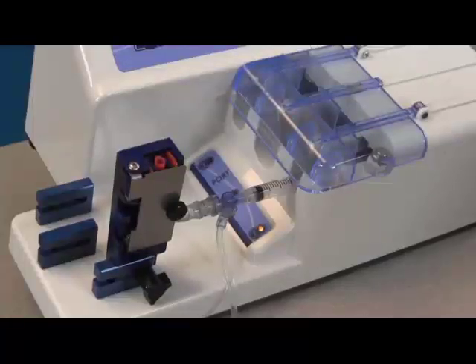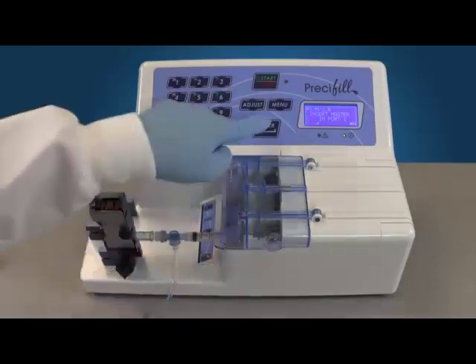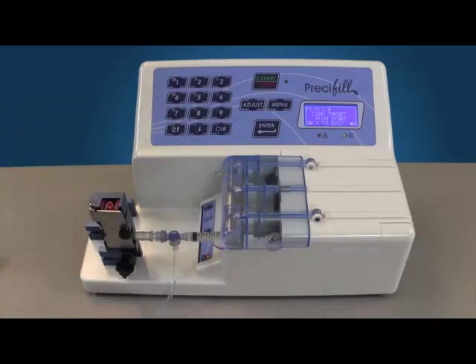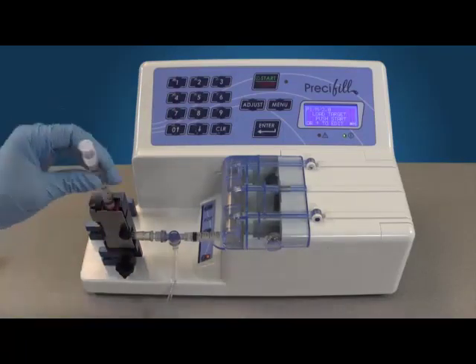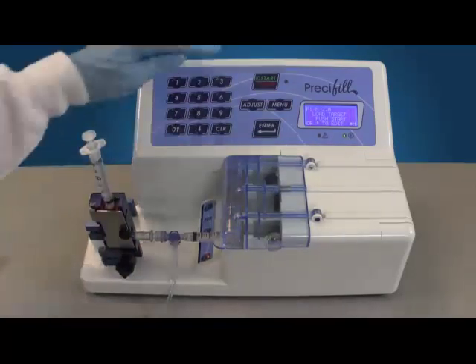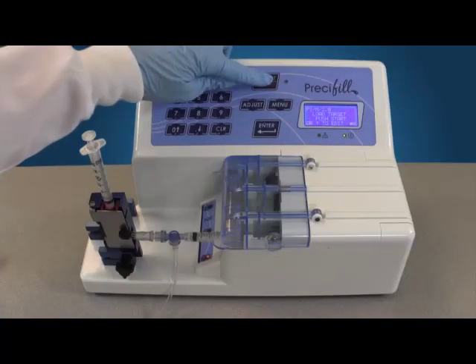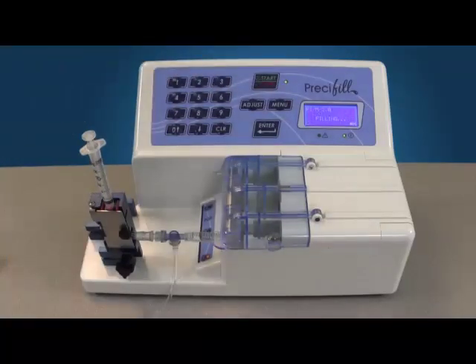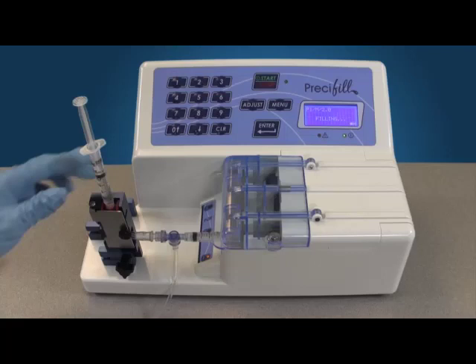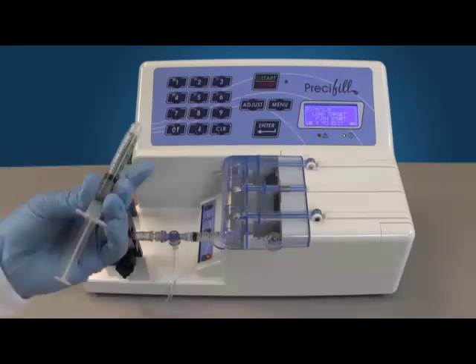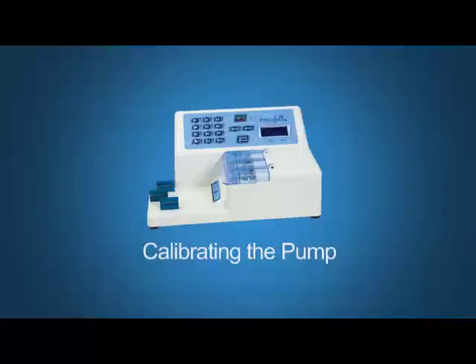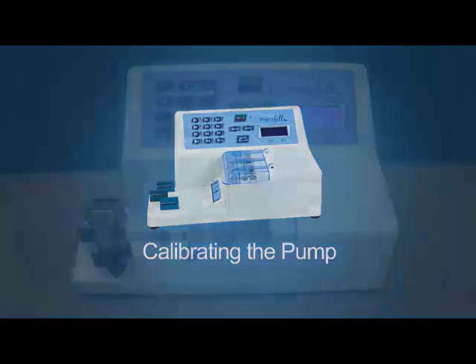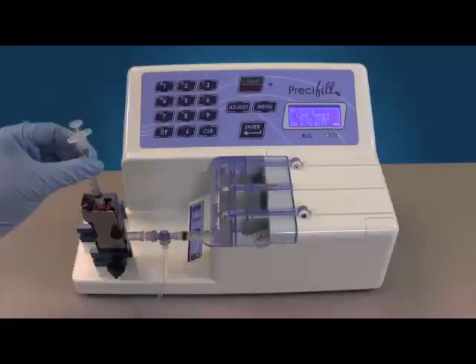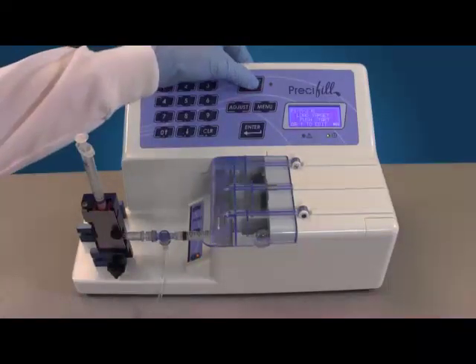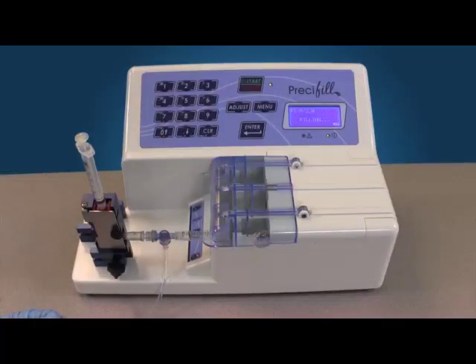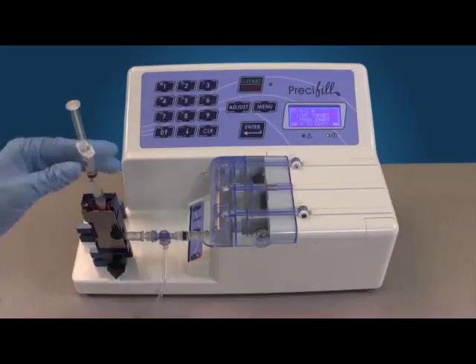Confirm the master syringe is placed in the correct port. Press enter. Lock the target syringe into the adapter tip. Fill the target syringe by pressing start. To calibrate the pump, run a sample IV syringe fill and verify the volume. Adjust if necessary.